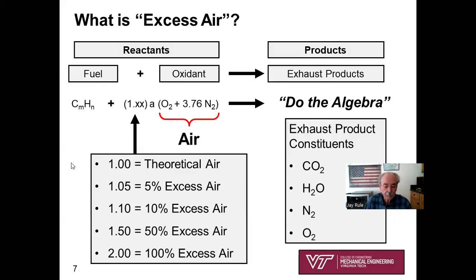air. And so it's my hope, instead of giving you a formula, I'm trying to give you by example to get into your head the relationship between this factor and the percent excess air. That's my hope of what you absorb from this slide. So 1.10 in this factor means 10% excess air.